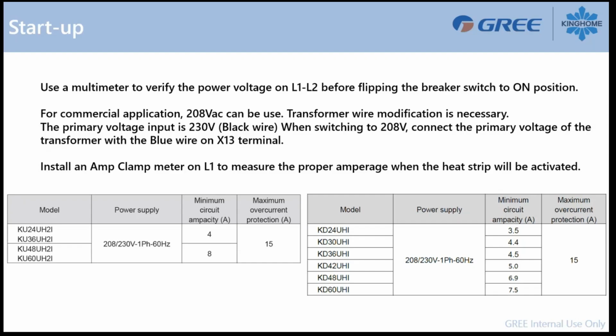Regarding the startup, it is important to take your measurement with your multimeter on L1, L2 before you flip the breaker switch to the on position. Make sure you have the proper voltage to the air handler. If it's a commercial application, sometimes you will have 208 volts in use. You can modify the transformer wire to the board if you're using 208.